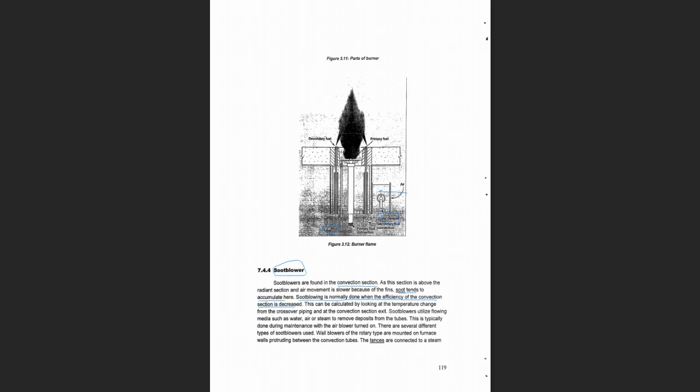تقريبا انا تكلمت عنها والله، بس انا متاكد اني تكلمت عنها، اللي هي السوت اللي هو الرماد والكربون الناتج عن عمليه احتراق الوقود يتراكم على الجدار الخارجي. جميل. ف just by observing stack temperature اللي هو من خلال مراقبه درجه حراره المدخنه الستاك تلاحظ ان درجه الحراره مرتفعه عن الحد الطبيعي. جميل. usually a high stack temperature indicates that you have a lot of soot accumulating on the tubes, especially in the convection section.